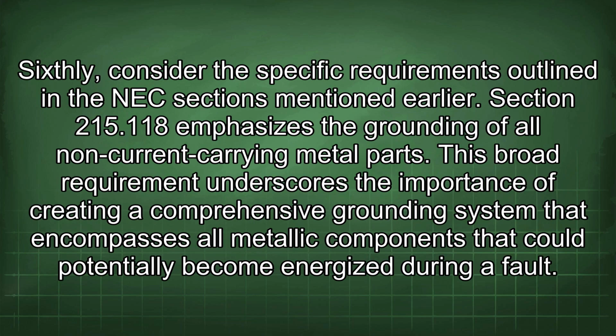Sixthly, consider the specific requirements outlined in the NEC sections mentioned earlier. Section 215.118 emphasizes the grounding of all non-current carrying metal parts. This broad requirement underscores the importance of creating a comprehensive grounding system that encompasses all metallic components that could potentially become energized during a fault.